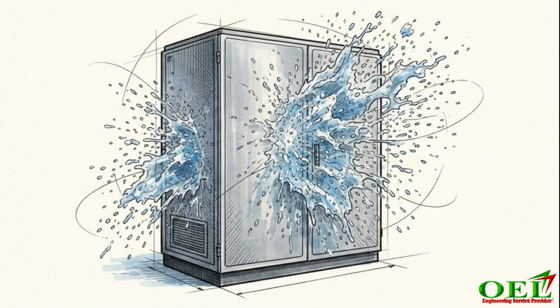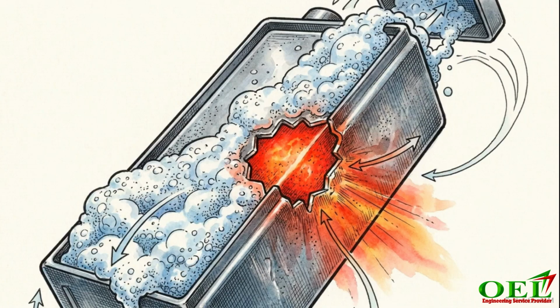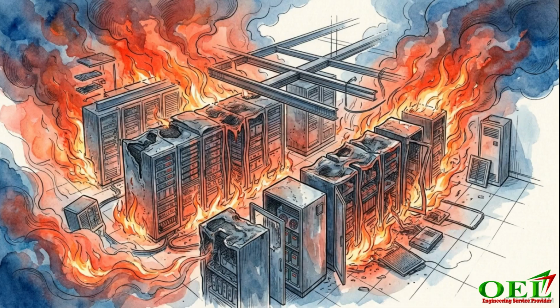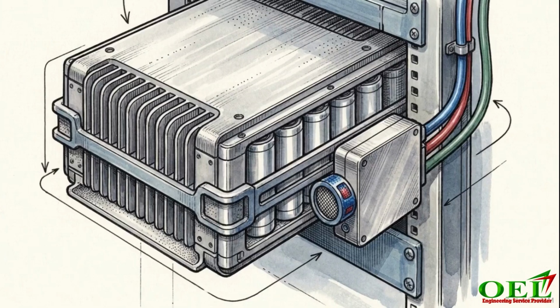Once that internal ignition happens, traditional reactive fire suppression systems are completely useless. Water and standard chemical foams cannot penetrate the cell casing to stop the chain reaction. For infrastructure operators, this means that waiting to see smoke or flames equates to accepting the total destruction of the entire facility. Protecting these investments requires stopping the fire before the very first spark is generated.